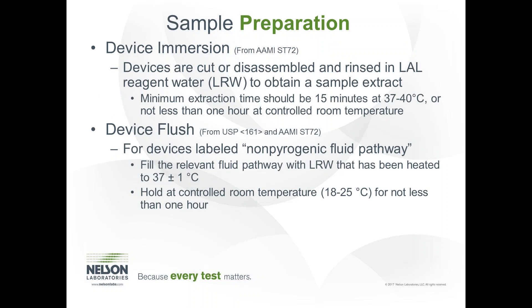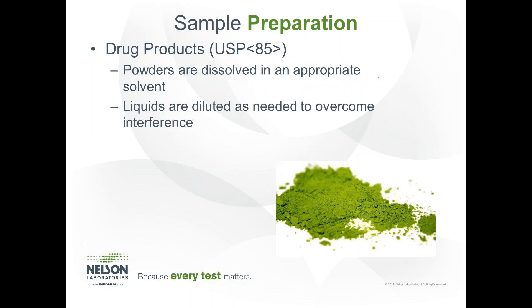Devices are typically disassembled and rinsed in LAL reagent water to obtain a sample extract. The minimum extraction time should be 15 minutes at 37 to 40°C, or not less than one hour at controlled room temperature. For devices that are predominantly a fluid pathway, the tubing is filled with endotoxin-free water heated to 37°C ±1 and held at controlled room temperature for not less than one hour. Powders are dissolved in an appropriate solvent and liquids can be diluted as needed to overcome interference.